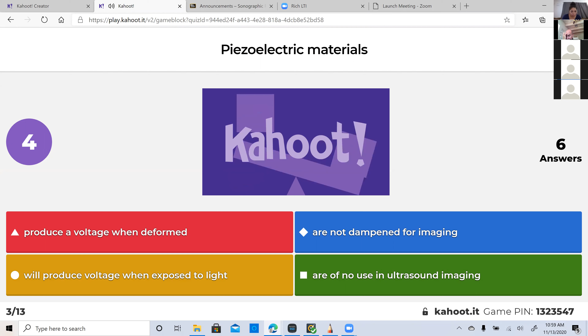Actually, I meant to give you guys more time to read all those. That was my bad. Yes, piezoelectric materials produce a voltage when deformed, and that's when the echo comes back. It slightly deforms, in other words, rings, and then produces. They are dampened for imaging. That's our damping layer.